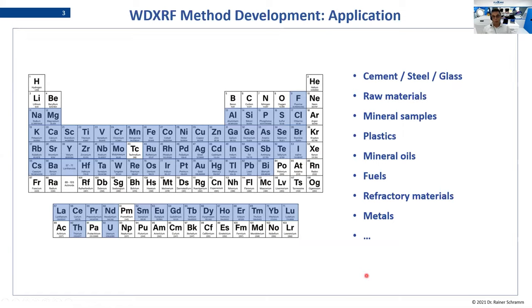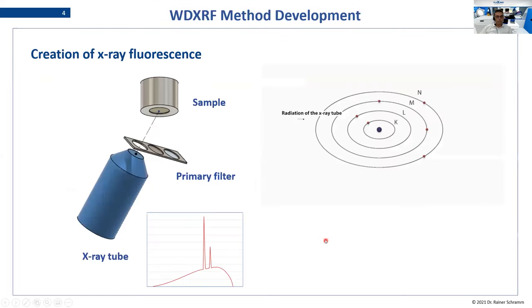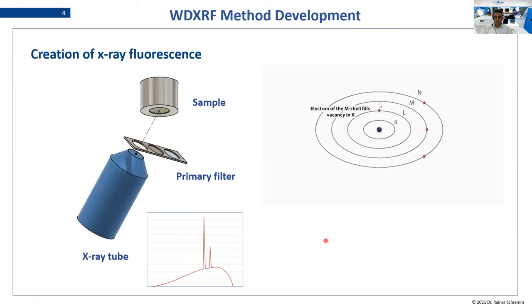XRF is used in many different applications — you can see here a big list. When we look at elements in the real world, from fluorine to uranium, this is the typical range people use Wavelength Dispersive XRF. You can also measure starting from beryllium, but then you need a specially equipped instrument. So there you have to make high efforts to get those elements measured.